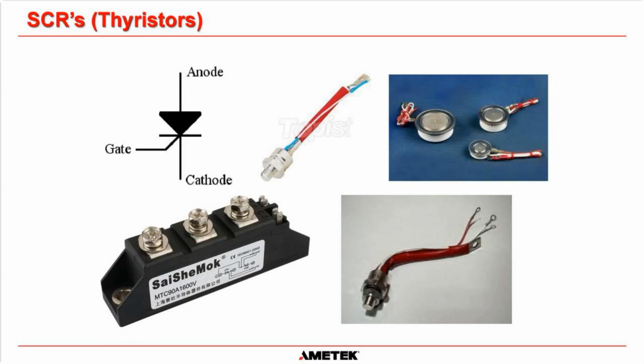If you have concerns about your supply system being affected by the harmonics reflected by your charger, then we would always recommend that you go for a 12-pulse charger, which is basically a charger that has 2 6-pulse bridges, 6 SCR bridges in there, 12 SCRs in total, that are offset by 30 degrees. Basically, one set of SCRs is connected to a delta transformer, and one set of SCRs is connected to a Y transformer, and they're offset by 30 degrees, and that really does lessen the amount of THD seen by the supply system. So if you are concerned, go for a 12-pulse charger.